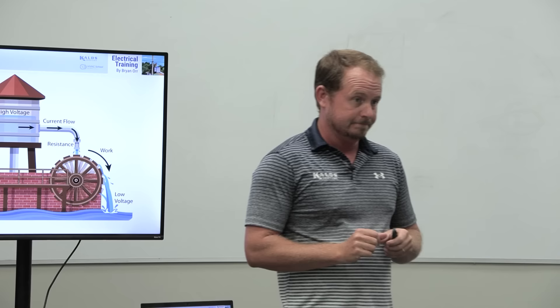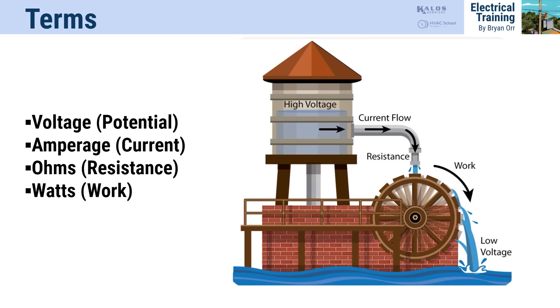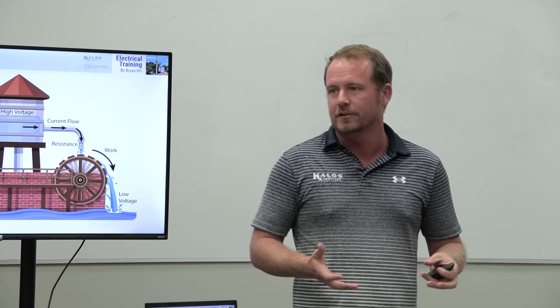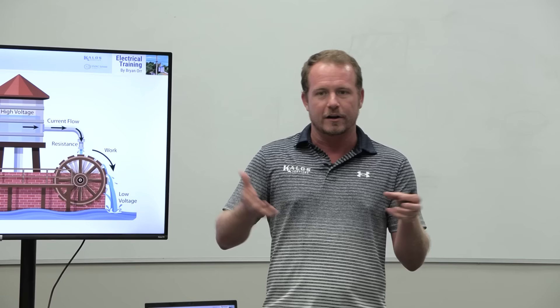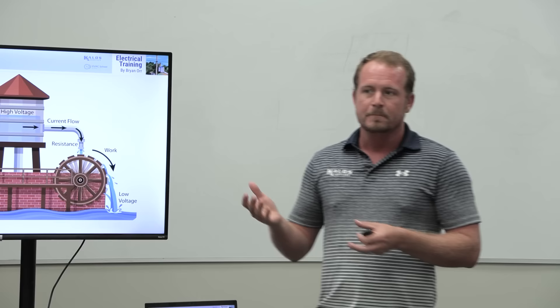Electrical resistance is a key thing to everything we do. If a circuit is drawing too much current, the resistance is too low. If it's drawing too little, there's too much resistance. That's it—there's no other magical thing. People argue that voltage could vary, and that's true: inverter drives, wrong voltage applied, utility fluctuations. But when something's drawing a lot of current, generally the resistance is too low—often because of a physically seized motor or, more commonly, a short circuit.